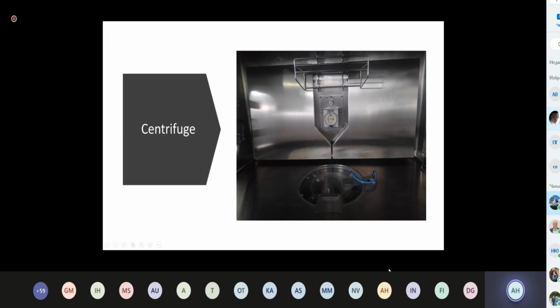So you will see here on the surface, we cut a hole and we install the centrifuge on the work surface. There is this blue little tube here, this is actually the compressed air supply. When you open up the cover, you can already see the rotor and the adapters here. As you can see, everything here is fully welded, very smooth stainless steel surface. At the cover, you will see this blue rim here.